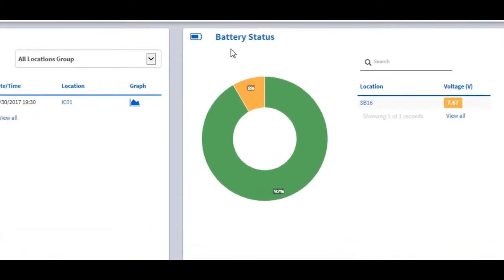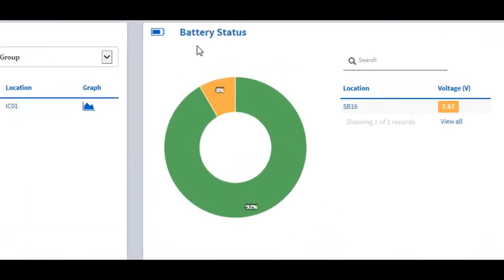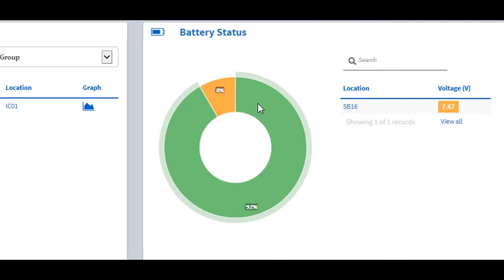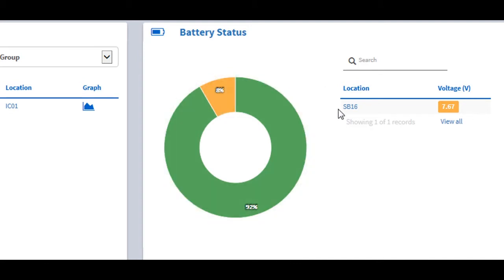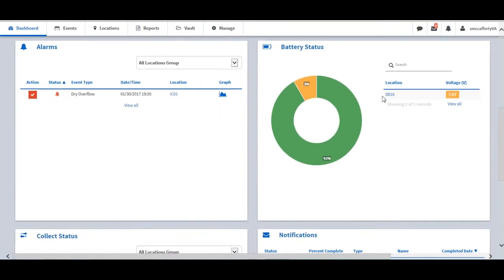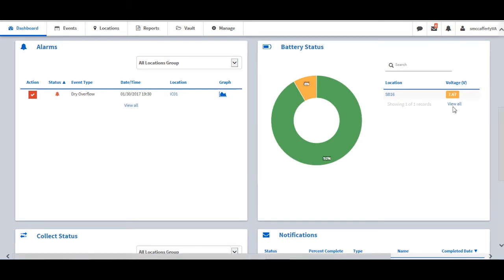The battery status tool displays the overall battery status of the meters. Green indicates good. Yellow indicates low — the battery voltage is within one volt of the low battery limit for the monitor model. Red indicates critical — the battery voltage is at or below the low battery limit. The list on the right ranks the locations with the ten most critical or low batteries. To access more battery status information, choose View All. This provides all location statuses, including Good.